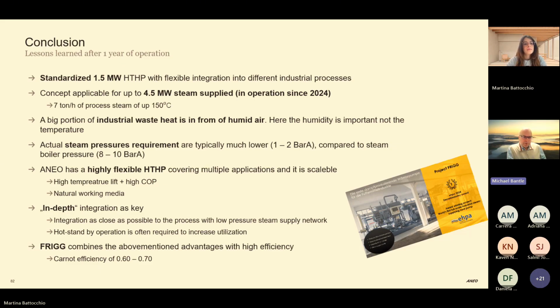Also important is the steam pressure requirements. Substituting a 10 bar boiler steam doesn't really make sense when you have to go with the heat pump to 180 degrees. If your excess heat is at 30 degrees, that gives you a COP of 1.5 or so, which isn't a good business case. But by doing this in-depth integration, we've shown that most processes, particularly in the food and feed industry, don't need 180 degree steam.